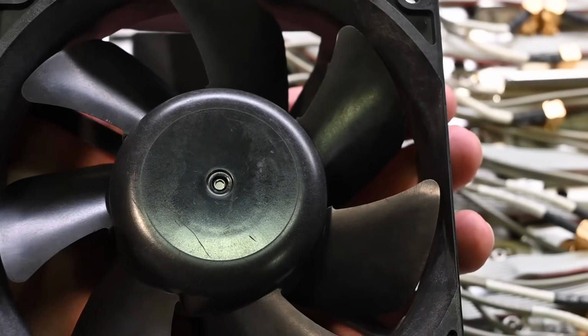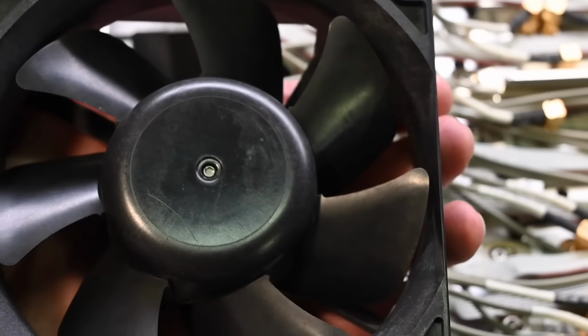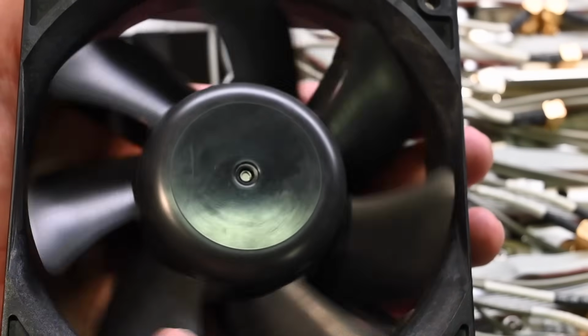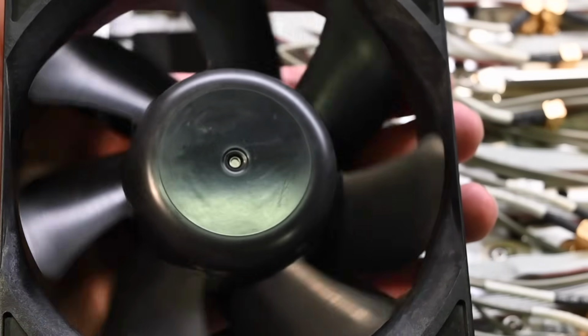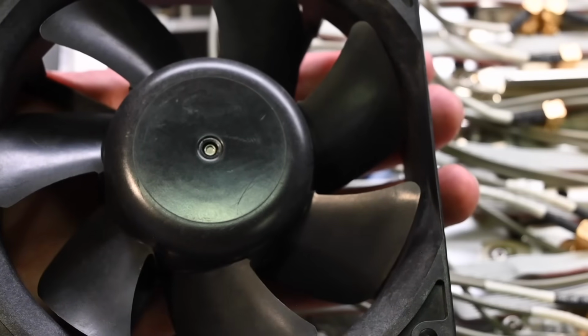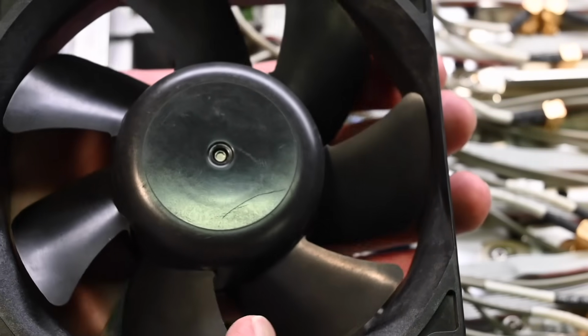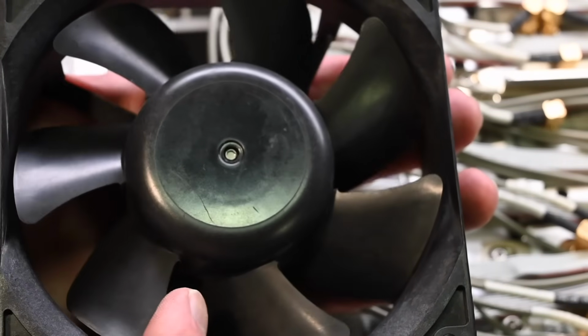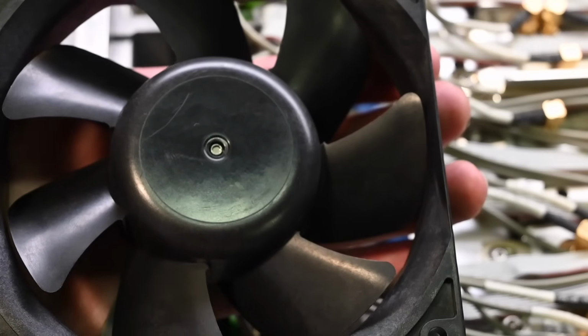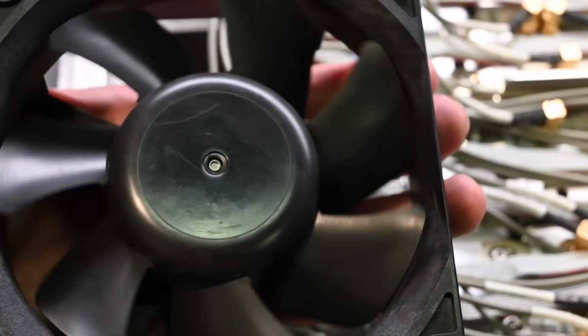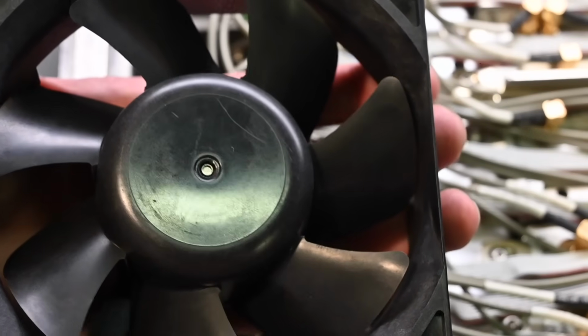And the motor seems to be in good condition. You know, it was quiet when it was running previously when we were testing. You can see when I turn the fan motor, it rocks back and forth very freely. That's always a good indication that the bearings are in good condition. If you turn the fan and it's stiff and you just have to push it around and it never rocks back and forth with that magnetism, that's an indication that the bearings are probably shot. So anyway, that's looking okay at this point.